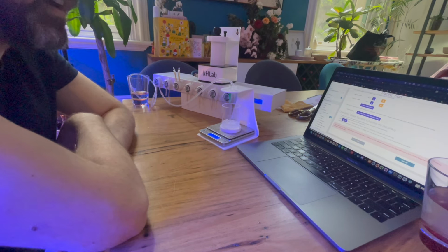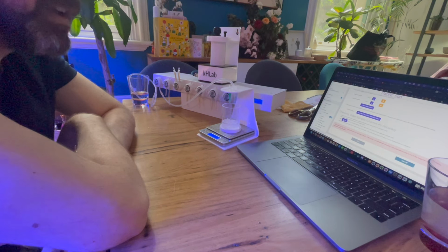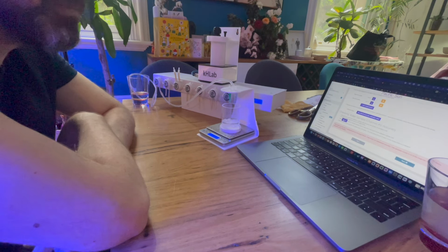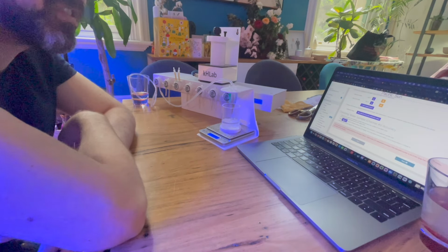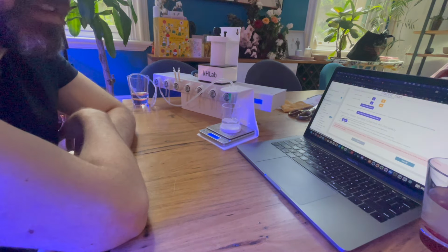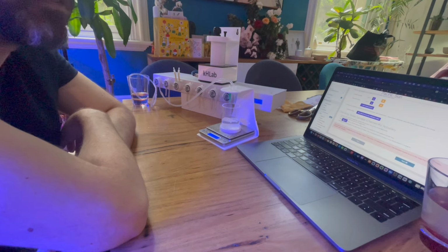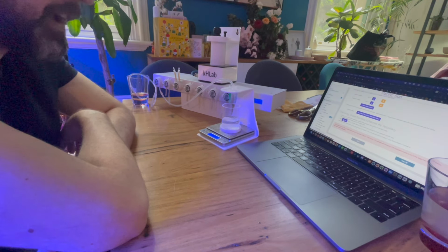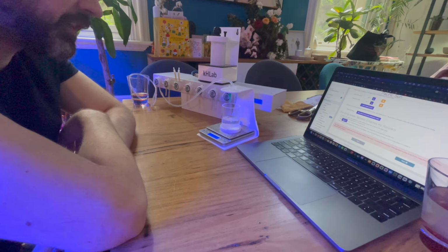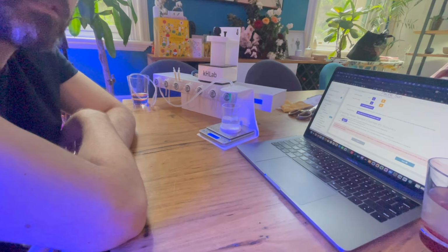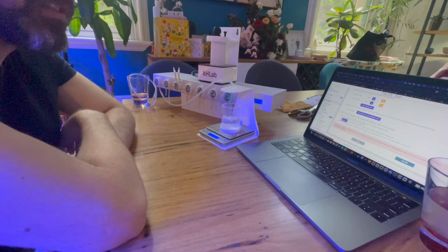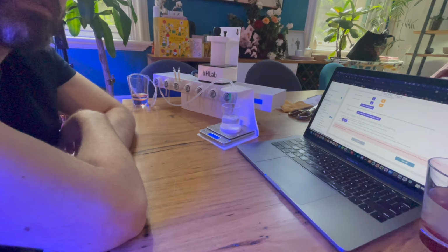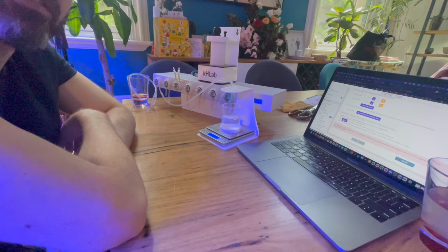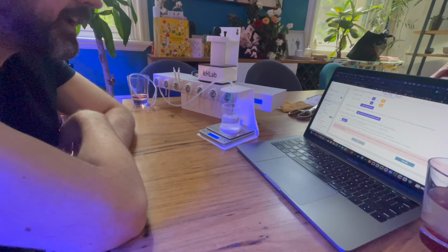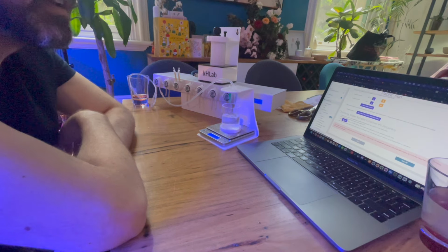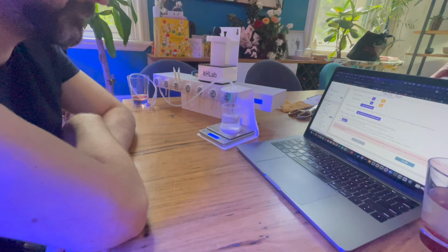So once you complete the process, the test result should be in the range of 69.2 to 70.8 mil, that's plus minus 1% of measurement accuracy, and you're good to go. If the test is not returning a result inside that 1% of measurement accuracy, you might have done something wrong. Maybe you recorded a value wrong, or you forgot to reset the scale properly at one time. That's okay, just do it again. Take your time with it until you get that calibration spot on.